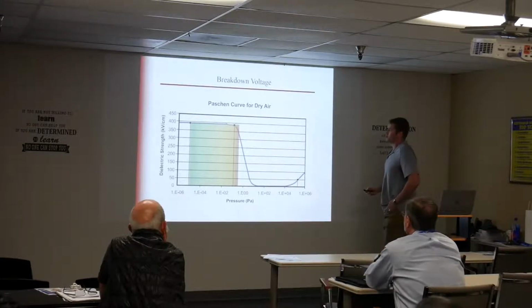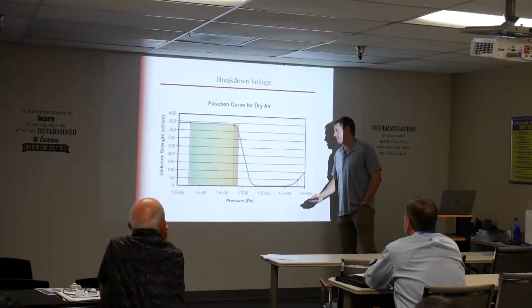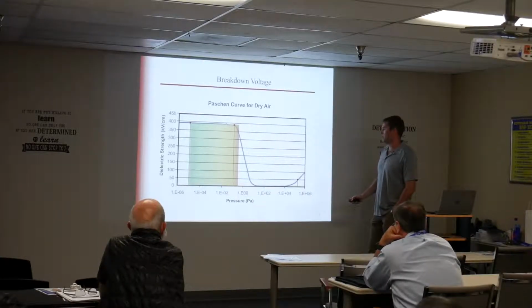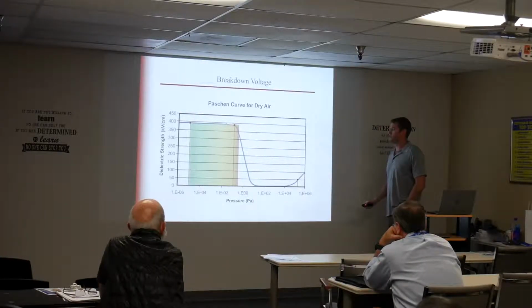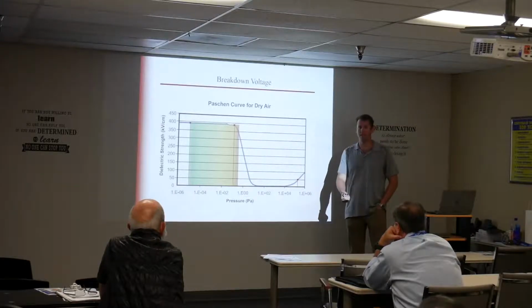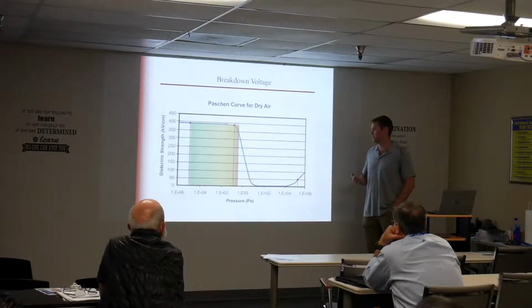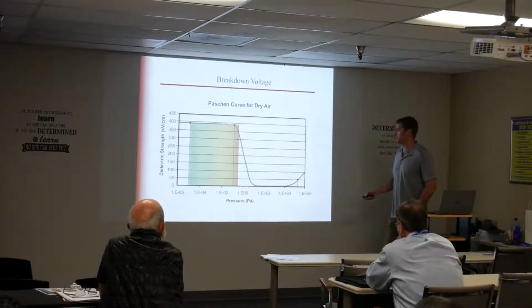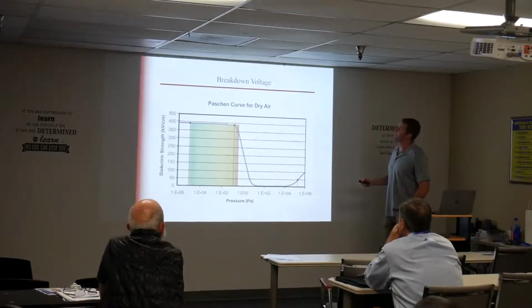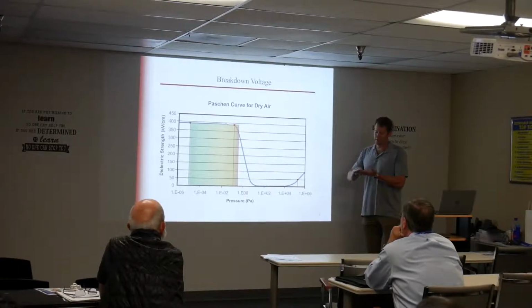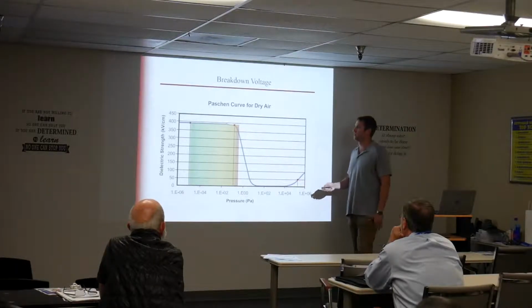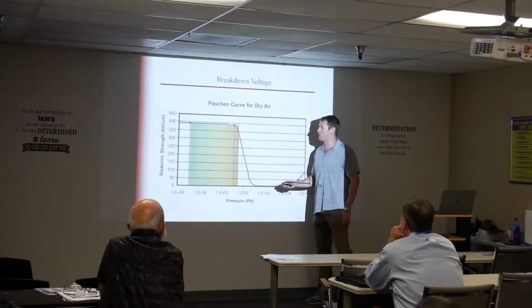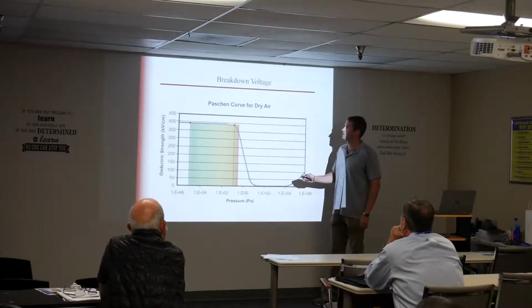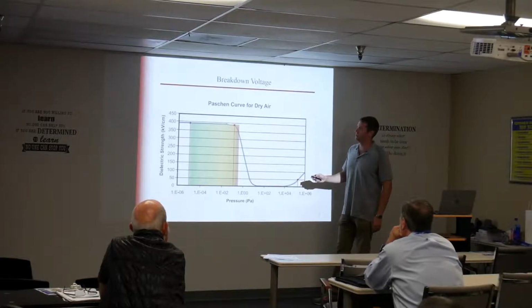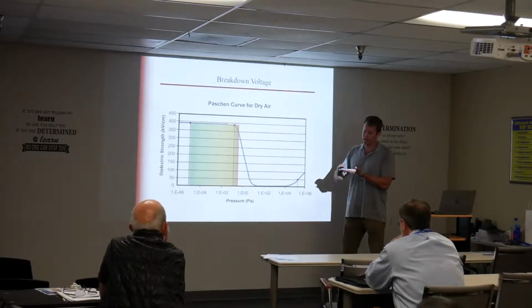This slide is important for interpreting the test results. The test is going to output a pressure in pascals. That's the unit of measurement we use. In the U.S. we're used to talking about PSI, but we're talking about vacuums, negative pressure, so we use pascals. And this is an equation that gives the breakdown voltage. What is the voltage necessary to draw an arc between two contacts? This is saying what that contact gap is, kV per centimeter. A centimeter is 10 millimeters. So that's the contact gap on these breakers.